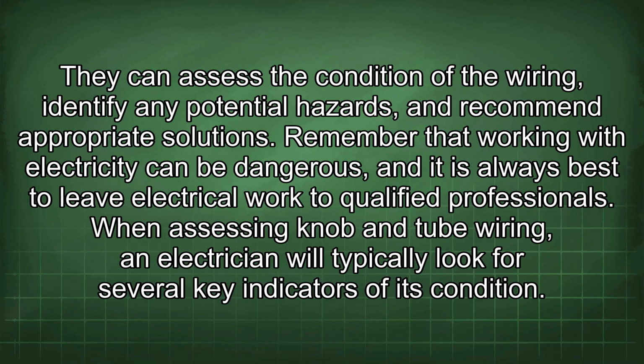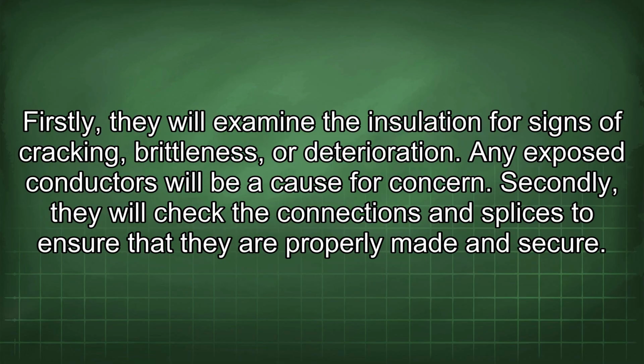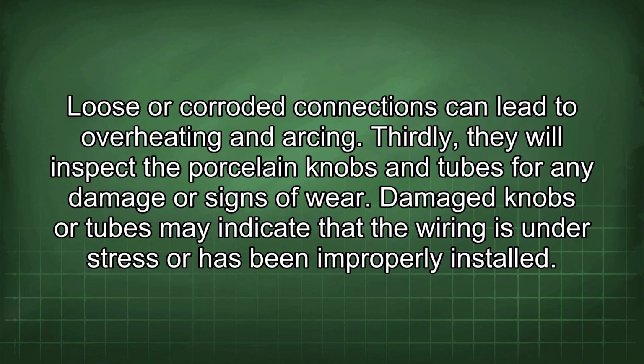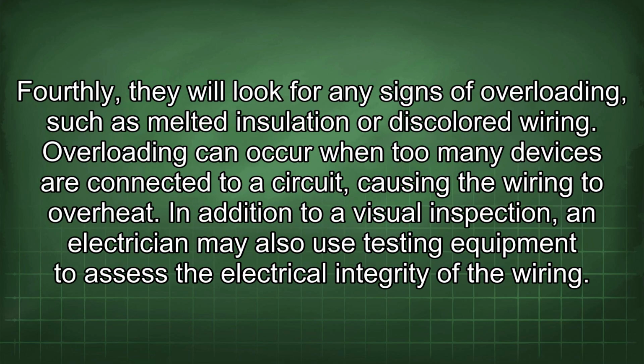When assessing knob and tube wiring, an electrician will typically look for several key indicators of its condition. Firstly, they will examine the insulation for signs of cracking, brittleness, or deterioration. Any exposed conductors will be a cause for concern. Secondly, they will check the connections and splices to ensure that they are properly made and secure. Loose or corroded connections can lead to overheating and arcing. Thirdly, they will inspect the porcelain knobs and tubes for any damage or signs of wear. Damaged knobs or tubes may indicate that the wiring is under stress or has been improperly installed. Fourthly, they will look for any signs of overloading, such as melted insulation or discolored wiring. Overloading can occur when too many devices are connected to a circuit, causing the wiring to overheat.